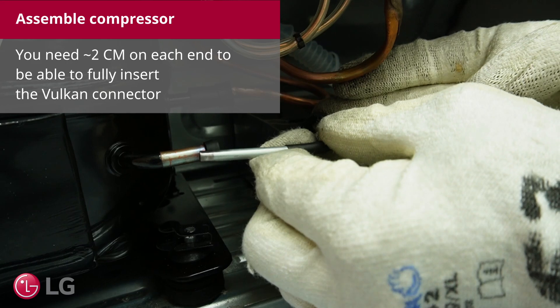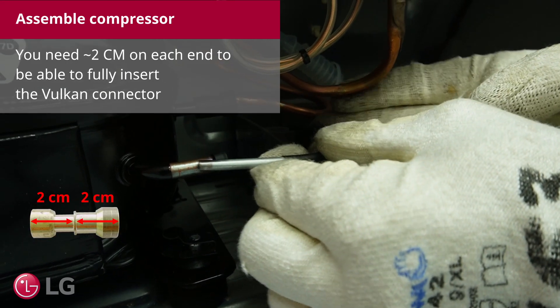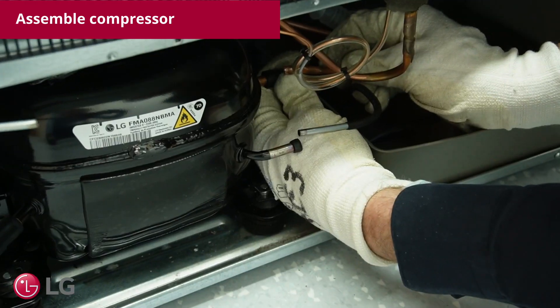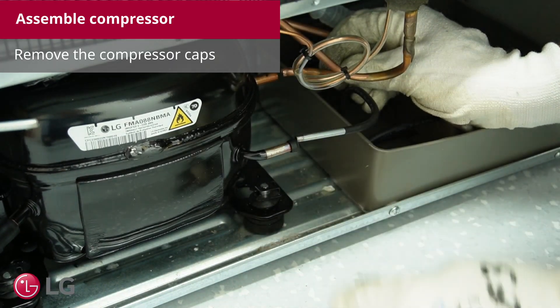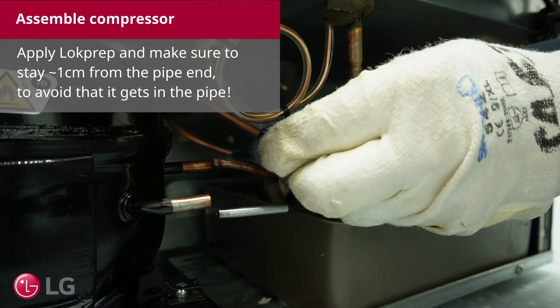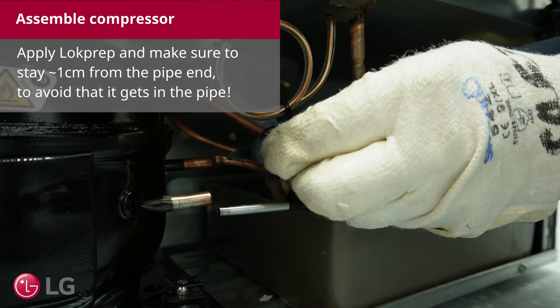Position the pipes straight towards each other. You need roughly 2 cm on each end to be able to fully insert the Vulcan connector. Remove the compressor caps. Apply Lokprep and make sure to stay around 1 cm from the pipe end to avoid that it gets into the pipe.